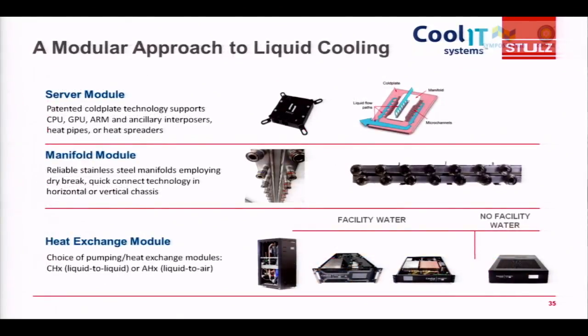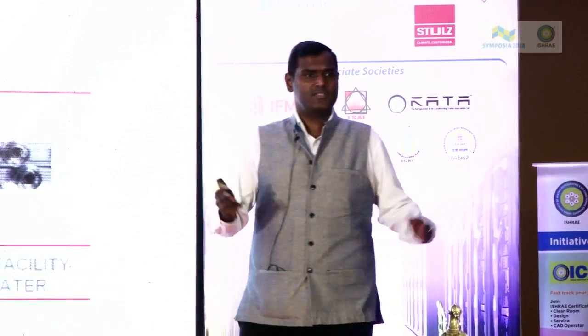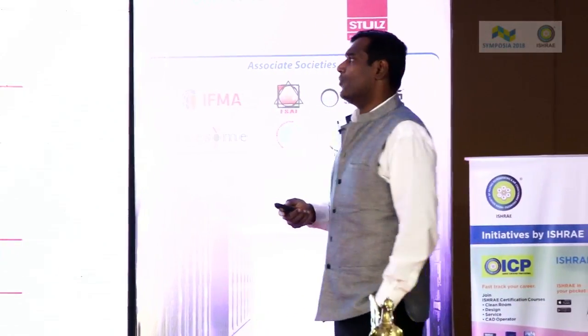And how does it work? Basically, you have three kinds of modules. One sits inside the server. One helps with the piping and gets the water into the server, and one is rejecting heat out. So it's pretty similar to air conditioning. If you look at the basics, the basics never change. Today we have a CRAC unit or a PAHU unit or a chilled water unit inside. You have a piping connection and you have a chiller outside. It's pretty much the same. It's just that everything is shrunk and everything is now much more efficient.